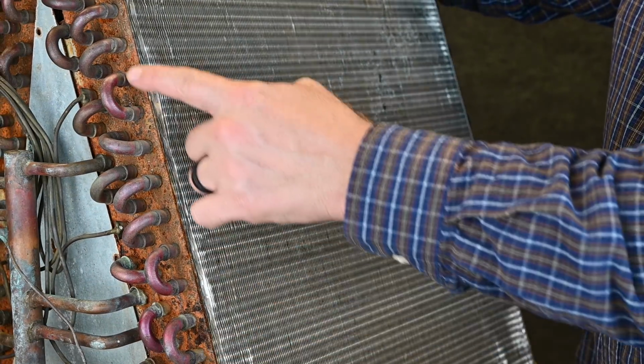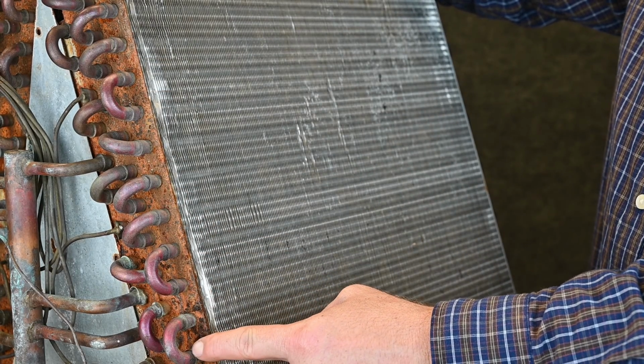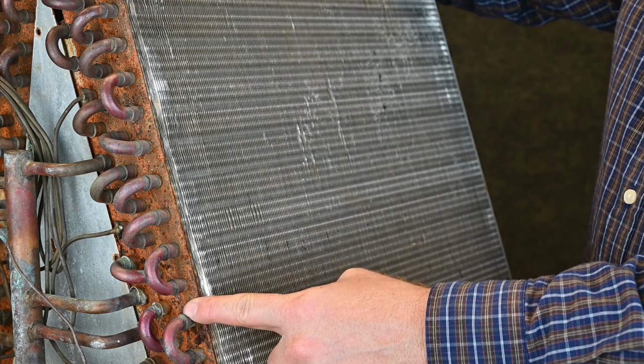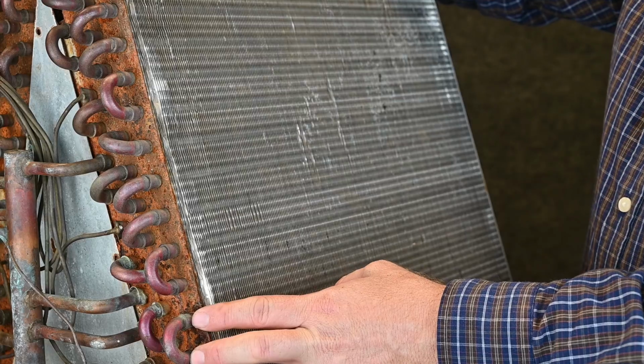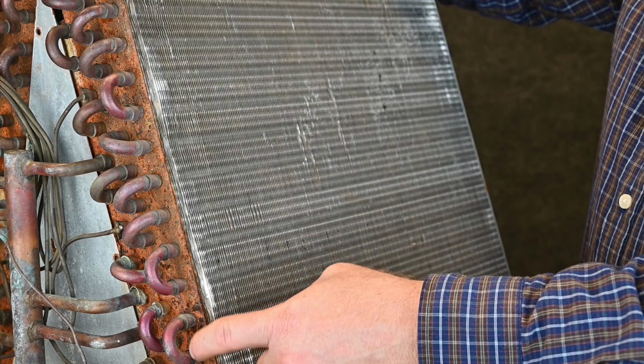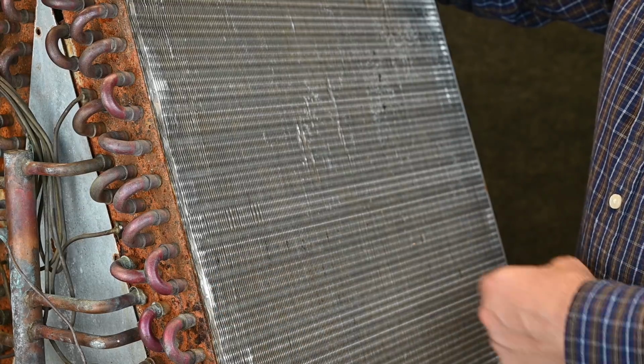If you figure that all of these were done at a factory at the exact same time, and I heat this up with my torch to fix this one, very easily this one could start leaking. Now in commercial units, it's much easier to do because they're spaced differently. But for residential, once you start trying to fix this leak, then you'll be back trying to fix this leak, or another leak someplace else.